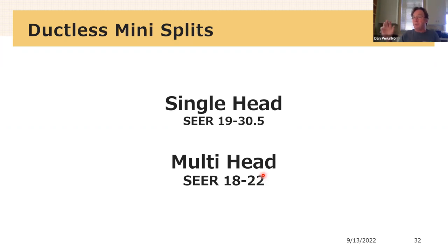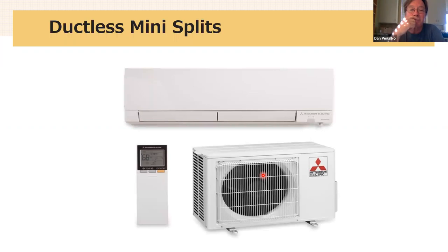Now, neither the 22 or the 30 tell you what the ultimate energy consumption is going to be. You just know going in that the 30 is more efficient than the 22, right? And the reason that they're not direct, like you can't calculate very directly how much power will be consumed, is there's too many other variables. This test is not great for California, and there's other things about the building that are involved. But relatively, it allows you to compare machines.